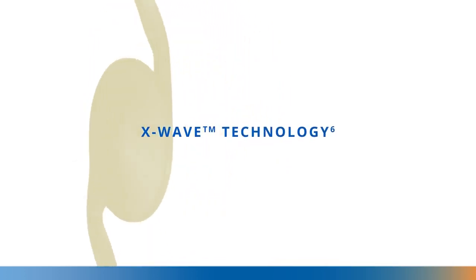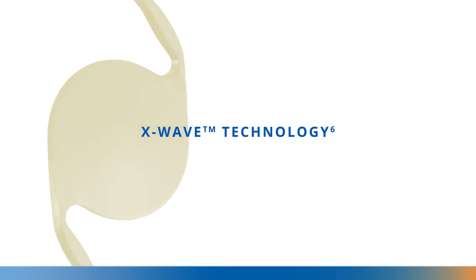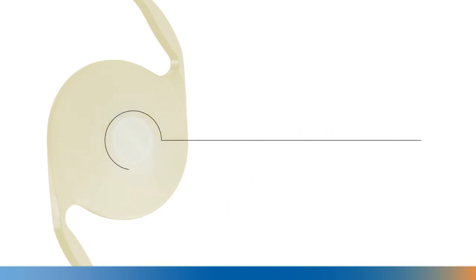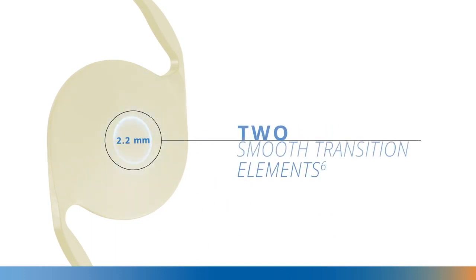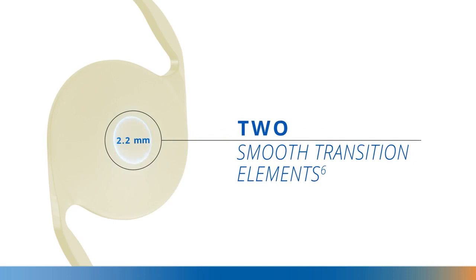What sets the unprecedented Clarion Vivity IOL apart is its proprietary non-diffractive X-wave technology, which simultaneously stretches and shifts the light without splitting it to create an extended focal range. X-wave technology features two smooth surface transition elements in the central 2.2 millimeters of the IOL.